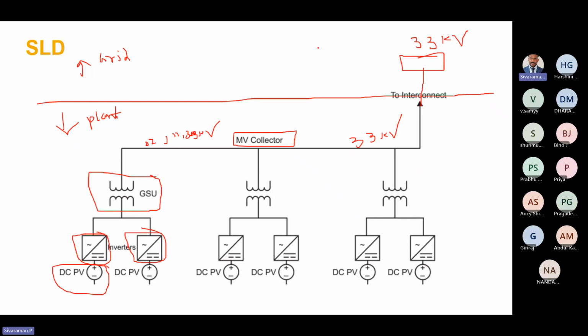Suppose the existing network is 132 kV. In that case, we shall have a power transformer rated 132 kV by 33 kV. The 132 kV side will be connected to the existing grid and the 33 kV side will be connected to our plant. Okay, so like this, the solar PV system looks in a broader perspective.